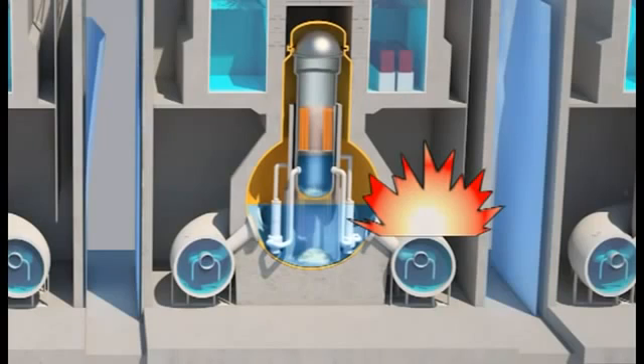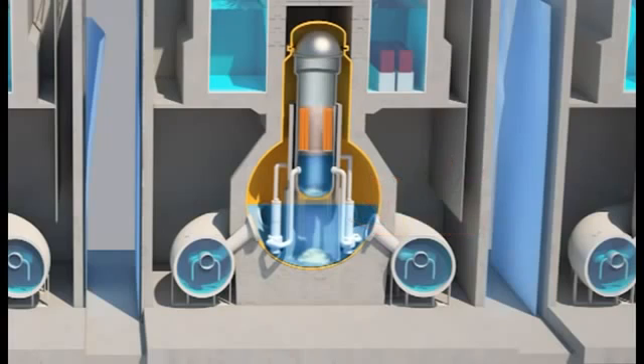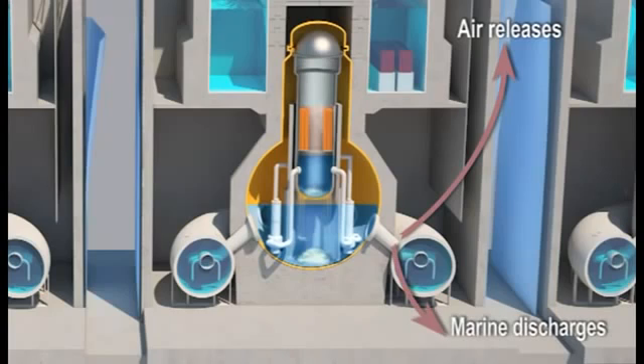The explosion took place inside the building. Operators have probably encountered difficulties depressurizing the containment, and the wet well suppression pool broke. This loss of leak tightness led to the discharge into the atmosphere of unfiltered radioactive elements and to the spreading of highly contaminated water in the buildings, leading to highly polluting discharges into the sea.